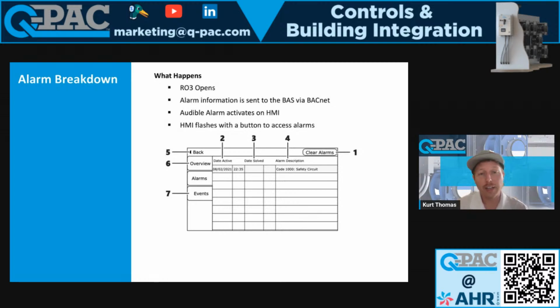So it's going to tell you exactly what the issue is. You'll see it in your system status. You'll see it if there's a fan alarm or an integrator alarm. One of those is going to light up and say, hey, something's wrong here. The HMI on the front of the control panel, there's going to be an audible alarm. It's going to make a high frequency buzzing alarm. So if you're around, you'll be able to hear it. And then the HMI is also going to flash, and there's going to be a button that flashes.